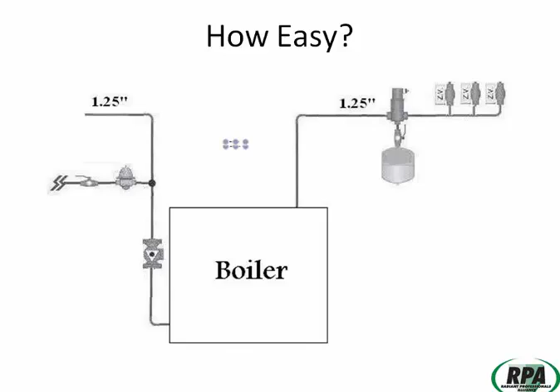I've got a question for you in regards to this drawing. Did this system have a tendency to overpressure itself quite a bit? I'm sorry, what was the question? Did this system have a tendency to overpressure itself quite a bit? Yes. I can see why. That pressure reducing valve at the inlet to that pump is guaranteed overpressurization, especially when it's pumping towards the expansion tank.